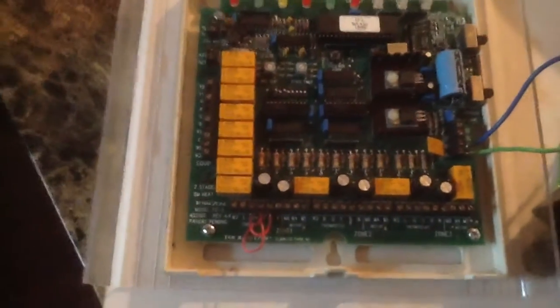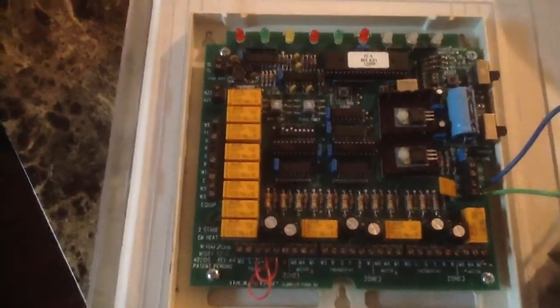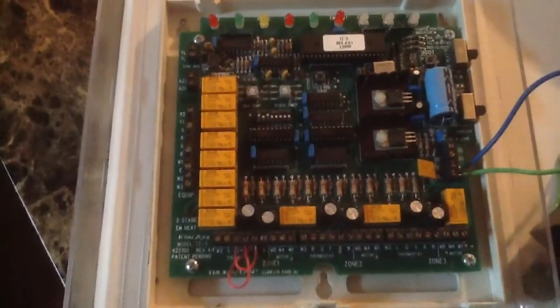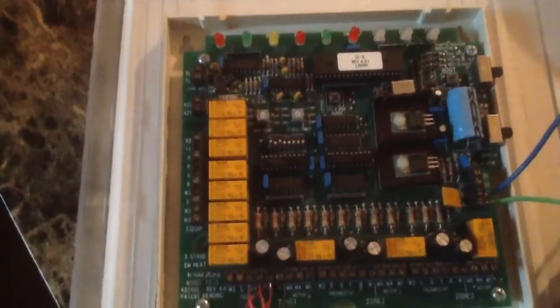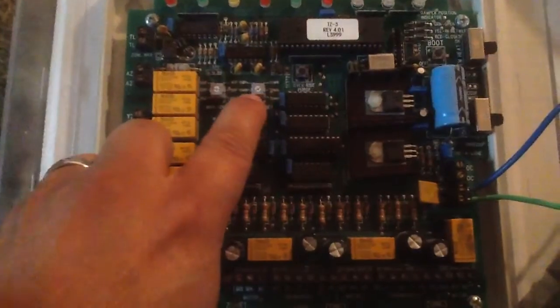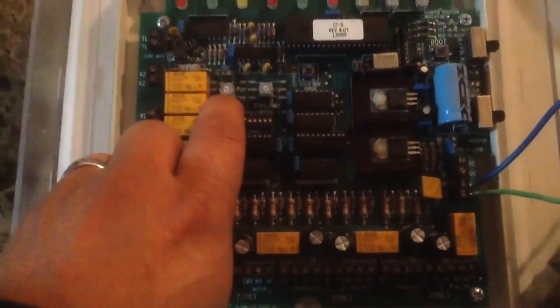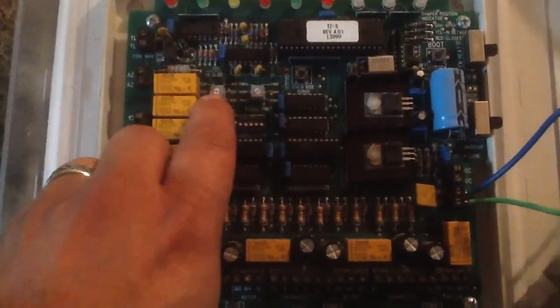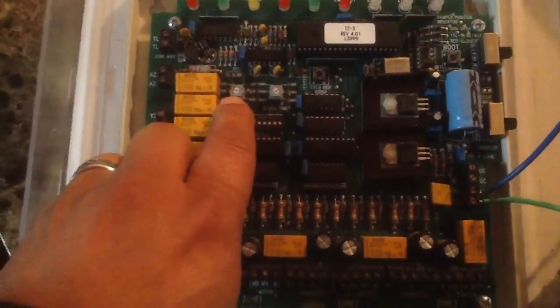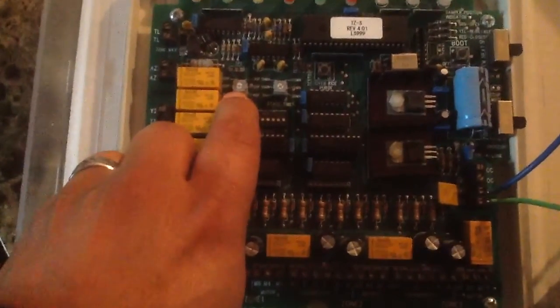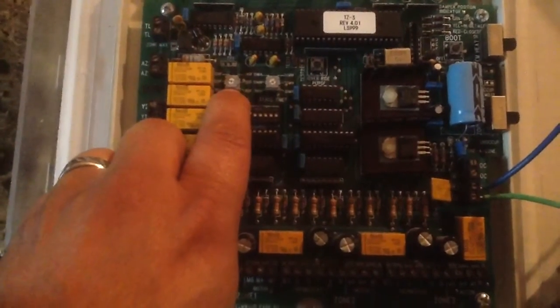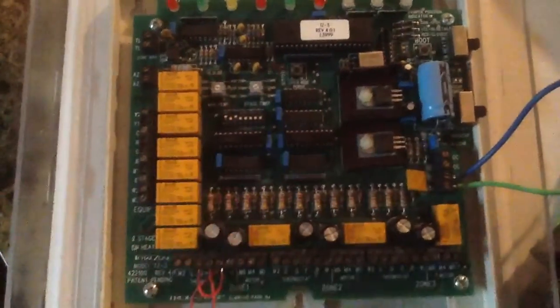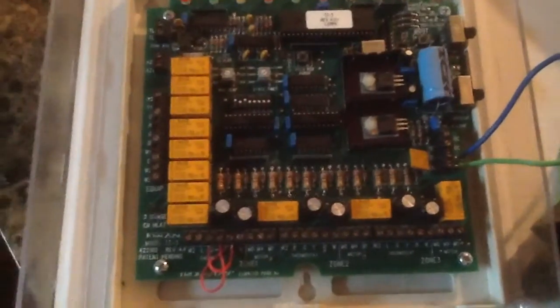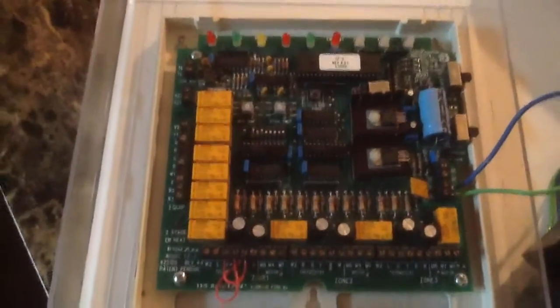And for the most part, guys, that's really all there is to it. Every zone board is different, everyone's set up differently and labeled a little differently. I know EWC gives you a lot more potentiometers. You have a lot more adjustments you can make to fine-tune the system. They give you an actual cooling limit, so if the temperature gets too low, to prevent freezing, you can set that. They give you a heating limit, a second stage heating limit, and so on and so forth. So I think EWC is a little more superior than this basic control zone board.